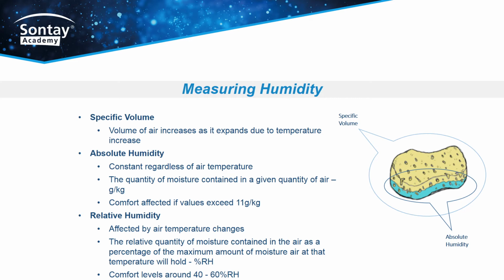Measuring humidity. There are 3 different types of humidity measurement. Specific volume. Volume of air increases as it expands due to temperature increase. Absolute humidity. Constant regardless of air temperature. The quantity of moisture contained in a given quantity of air, grams into kilograms. Comfort affected if values exceed 11 grams per kilogram. Relative humidity. Affected by air temperature changes. The relative quantity of moisture contained in the air as a percentage of the maximum amount of moisture at that temperature it will hold. That's a percentage of RH. Comfort levels are around 40 to 60% RH.